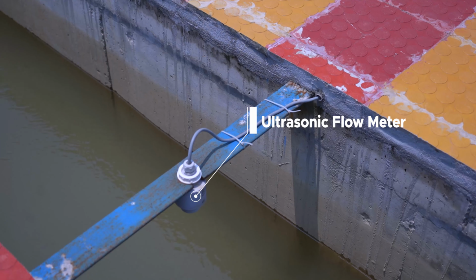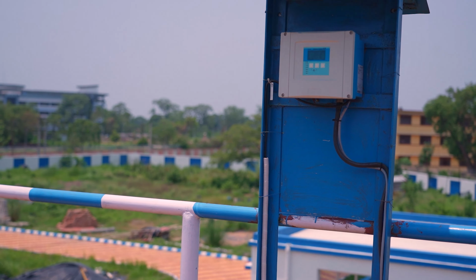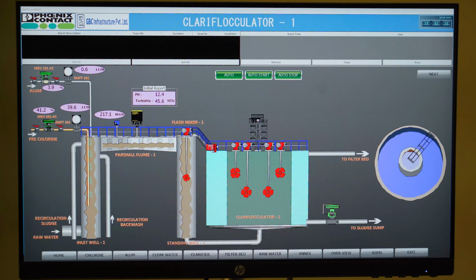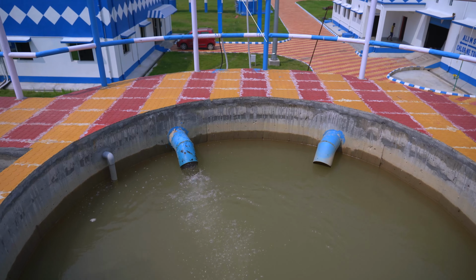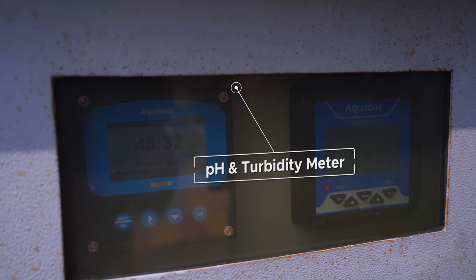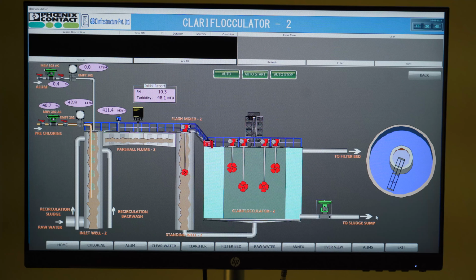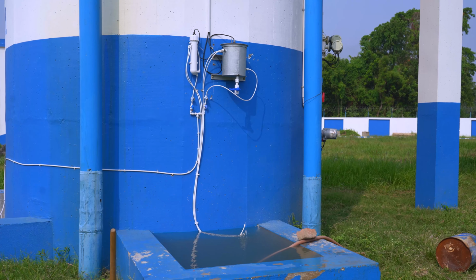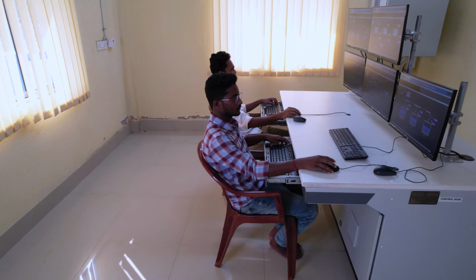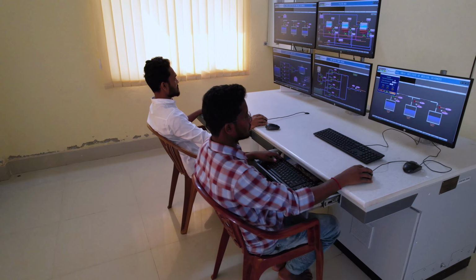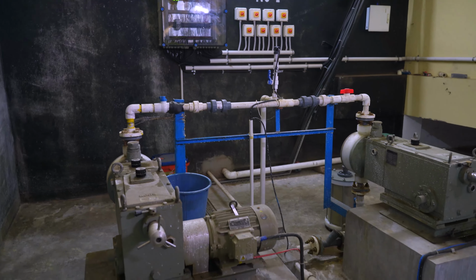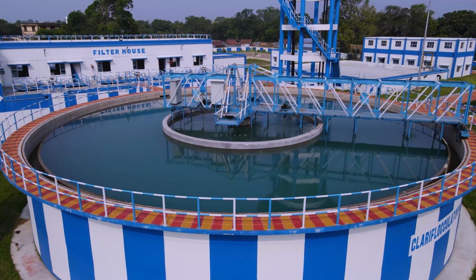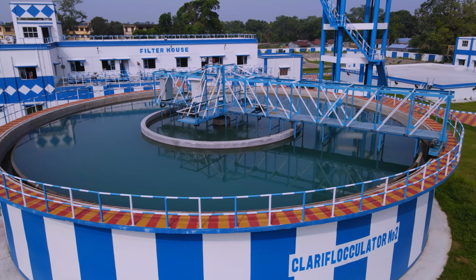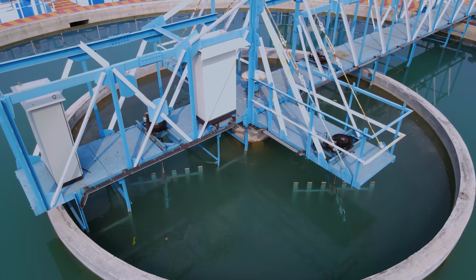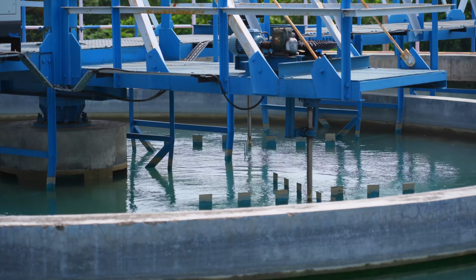The ultrasonic flow meter fitted on the Parshall flume gives us the volume of water that enters into the 2 clarifloculator. Online pH meter and turbidity sensor measures the initial quality of raw water through the arrangement of flow cell. The acquired data helps the operator to decide the right amount of dosing of alum and chlorine, which not only cut down the wastage of chemicals but also ensures the success of next step, flocculation.